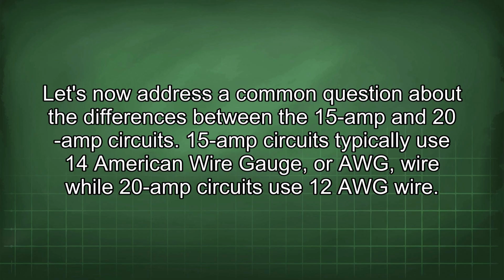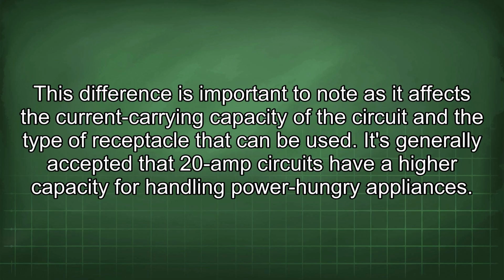Let's now address a common question about the differences between the 15-amp and 20-amp circuits. 15-amp circuits typically use 14 American Wire Gauge, or AWG, wire, while 20-amp circuits use 12 AWG wire. This difference is important to note as it affects the current carrying capacity of the circuit and the type of receptacle that can be used. It's generally accepted that 20-amp circuits have a higher capacity for handling power-hungry appliances.